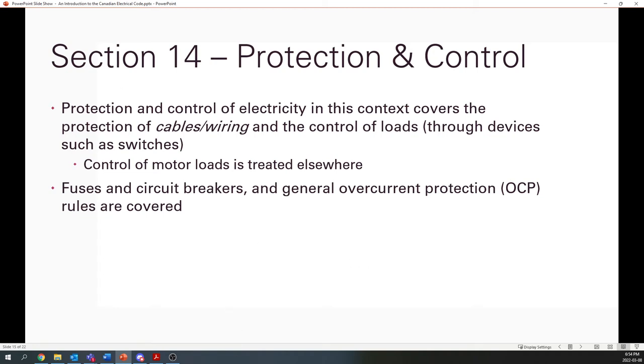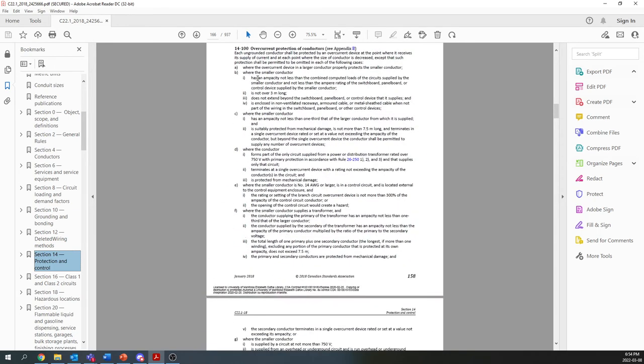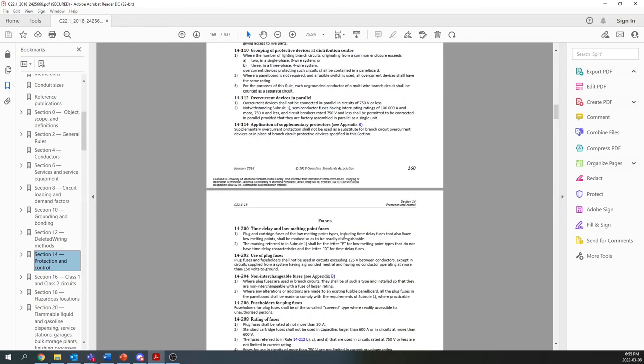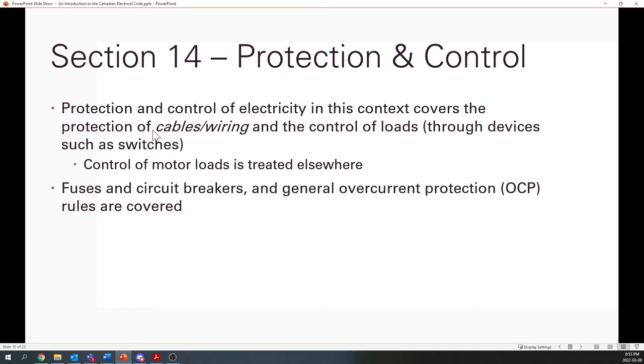So for section 14 here, general requirements, overcurrent protection. This lays out the theory of how overcurrent protection is done, ground fault protection, rating of devices, and all that sort of stuff. There are lots of rules on how devices are rated. There are certain situations where you need to use a more conservative rating than others. I should also mention briefly that protection of an electrical circuit is not there to protect the load, with the exception of ground fault protection, which can be there to protect either the load or you.